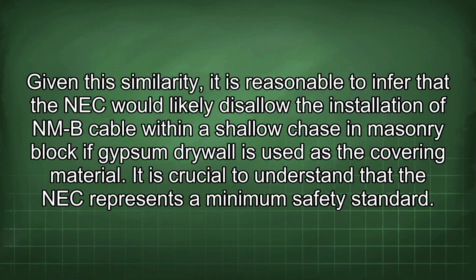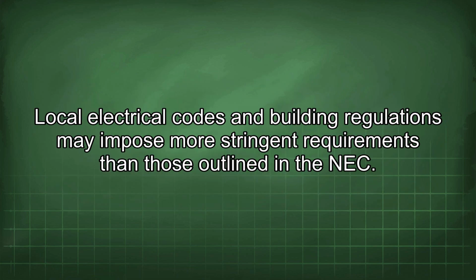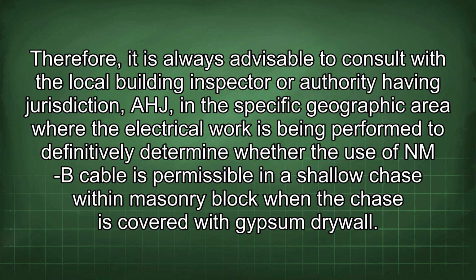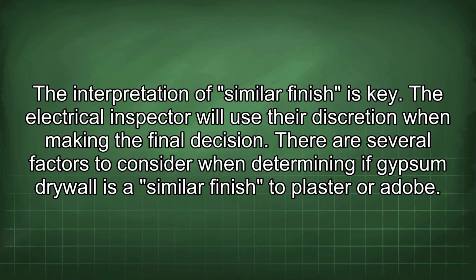It is crucial to understand that the NEC represents a minimum safety standard. Local electrical codes and building regulations may impose more stringent requirements than those outlined in the NEC. Therefore, it is always advisable to consult with the local building inspector or authority having jurisdiction (AHJ) in the specific geographic area where the electrical work is being performed to definitively determine whether the use of NMB cable is permissible in a shallow chase within masonry block when the chase is covered with gypsum drywall. The interpretation of similar finish is key. The electrical inspector will use their discretion when making the final decision.